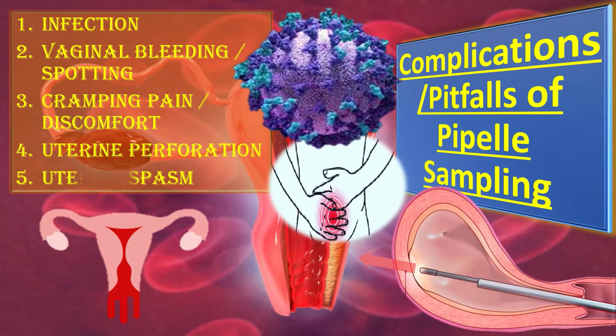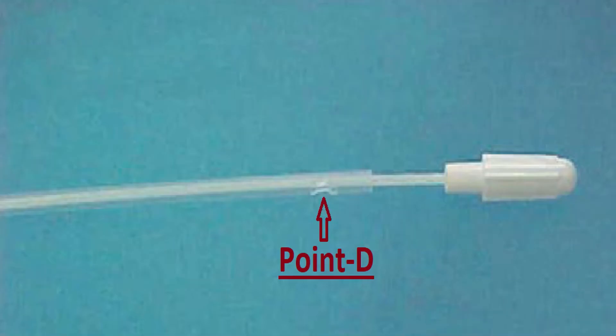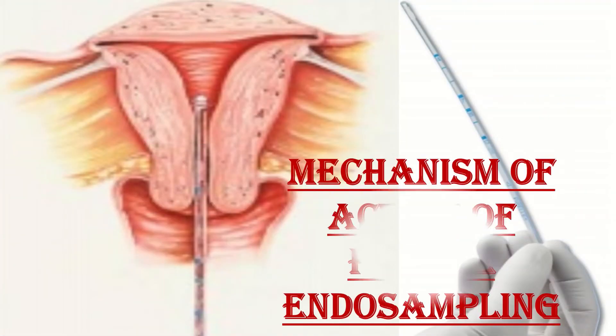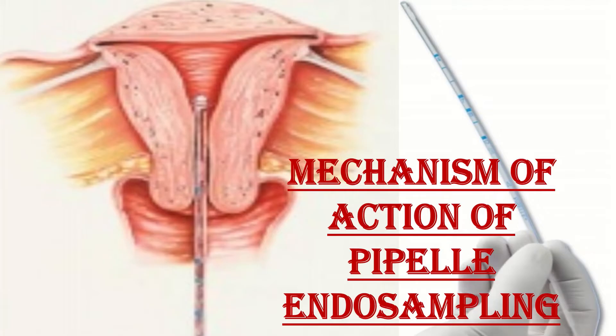Point D is an indentation in the pipelle endosampler located one centimeter from its proximal end, preventing the piston from being totally withdrawn from the sheath. The mechanism of action is that rapid movement of the piston within the sheath from its fully inserted position to its maximum retracted position creates negative pressure within the sheath, which drains mucosal tissue through the aperture in the lumen of the sheath.